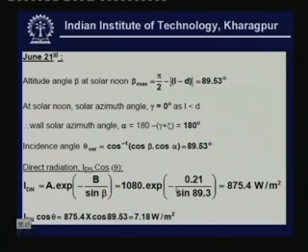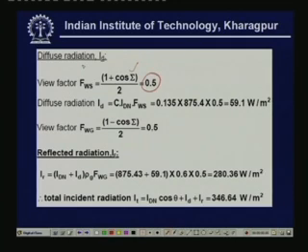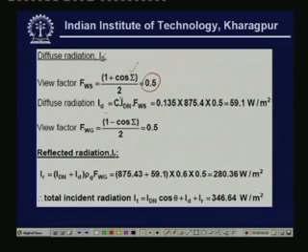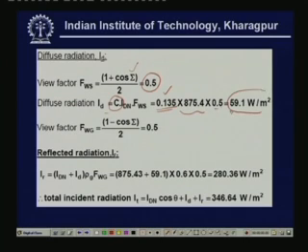Next we find the diffuse radiation. The view factor for the sky is given by (1 + cos(epsilon))/2, where epsilon is 90 degrees, so the view factor F_WS = 0.5. Based on the ASHRAE model, diffuse radiation I_D = C × I_DN × F_WS, where C = 0.135 for summer. Substituting I_DN = 875.4 and F_WS = 0.5, the diffuse radiation works out to be 59.1 W/m².